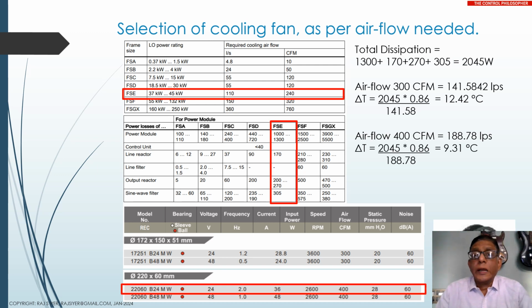Now this is not a good idea. So we go for a higher rated cooling fan. Let's see what happens with airflow of 400 CFM, which gives you 188.78 liters per second. In this case, you see that the delta T now falls down to 9.31 degrees centigrade. This is the way you have to do it.